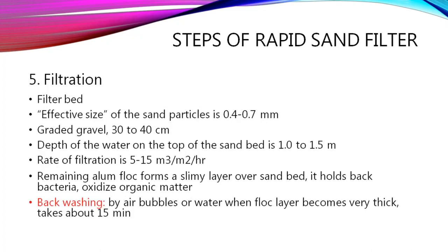After sedimentation, water is sent to the filtration bed. The key difference from slow sand: the flocculation, sedimentation, and coagulation steps happen separately before filtration. In rapid sand, sand particle size is 0.4 to 0.7, gravel is 30 to 40 centimeters, water on top is 1 to 1.5 meters, and the rate of filtration is 5 to 15. Remaining alum flocs form a slimy layer over the sand bed, holding back bacteria and oxidizing organic matter - acting mechanically rather than biologically.